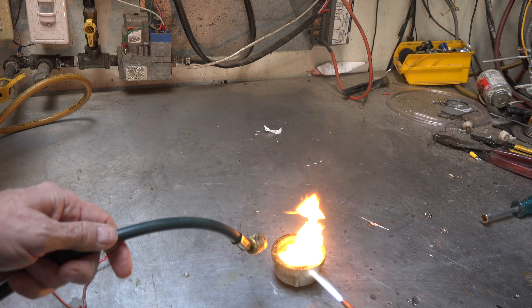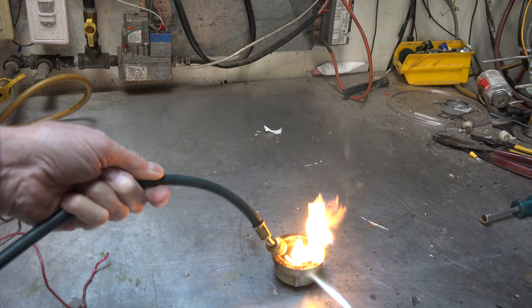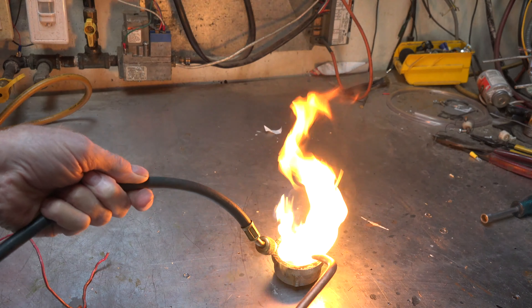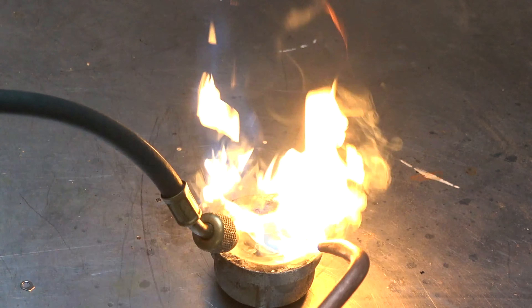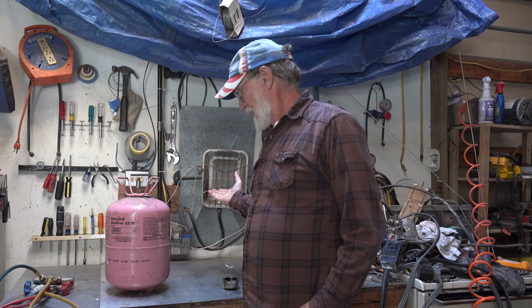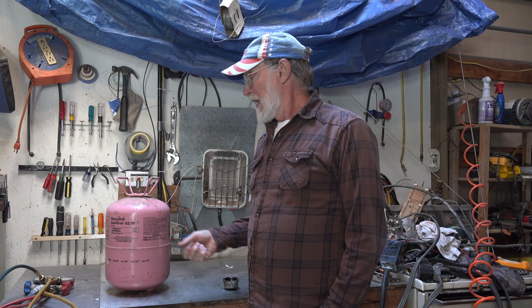Here I have some oil — this is refrigerant oil that I have preheated. Yeah, more than anything else it just puts it out. Can I say this stuff is flammable? Well, obviously I can't say for all conditions, but even in the presence of hot oil it really didn't do much. It's more like blowing air across it or something like that. I wouldn't be too concerned about this stuff being flammable. I just don't think it's an issue.